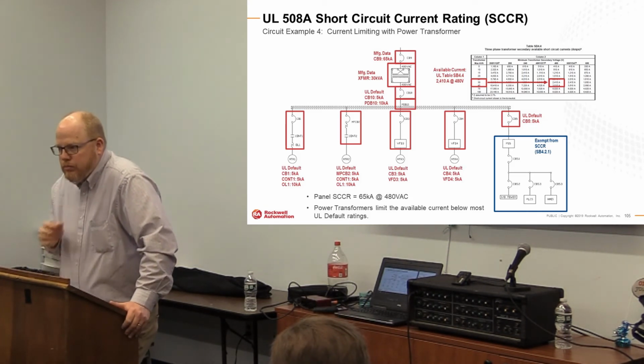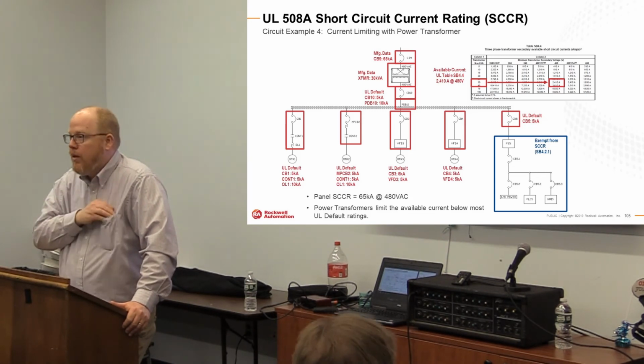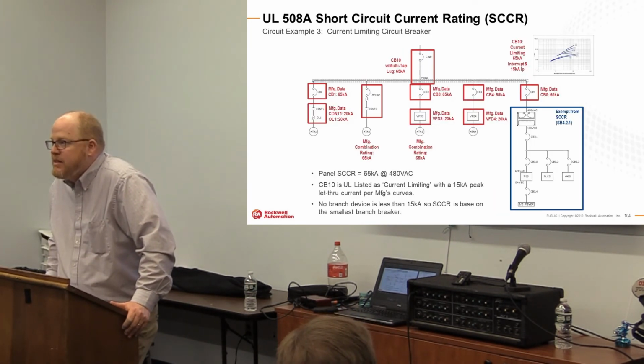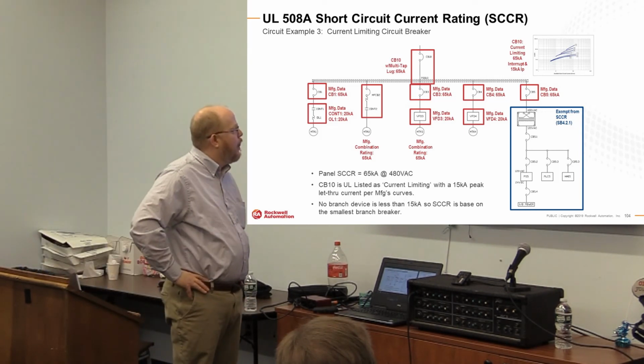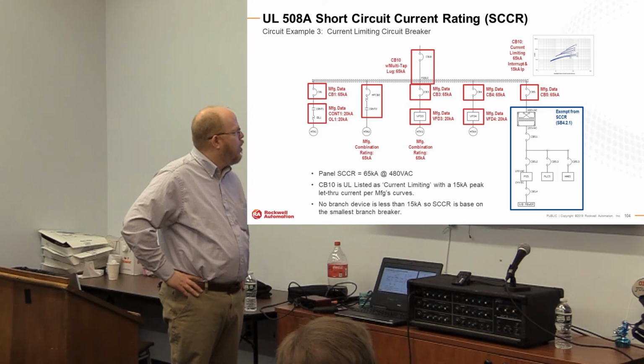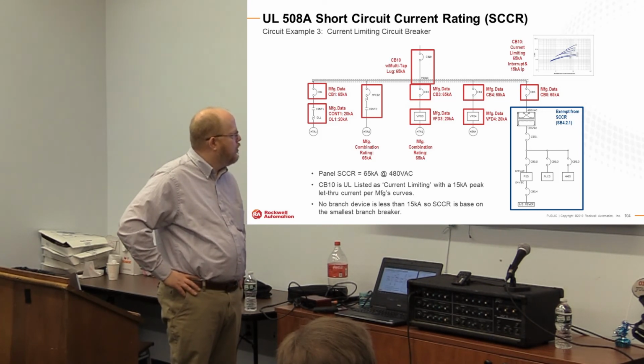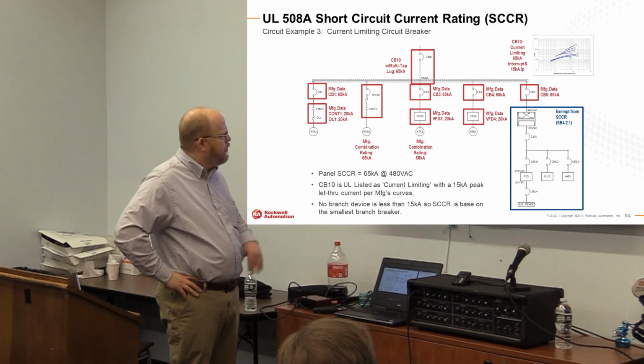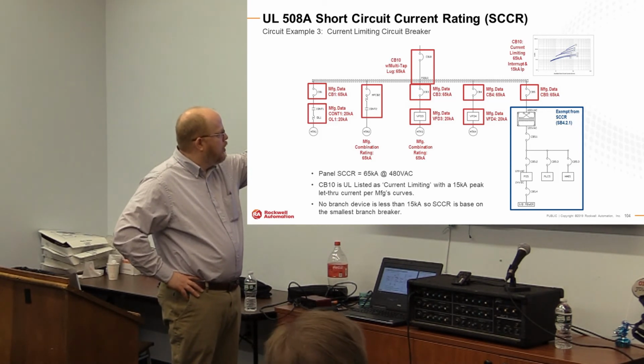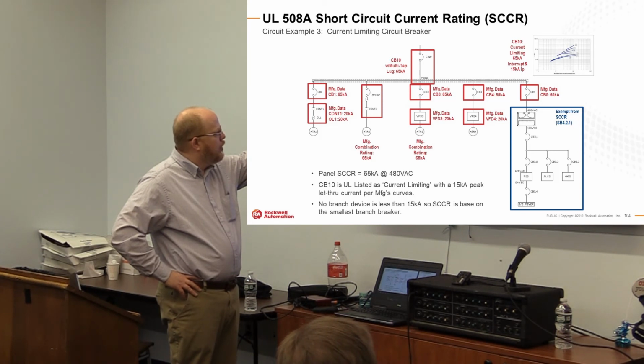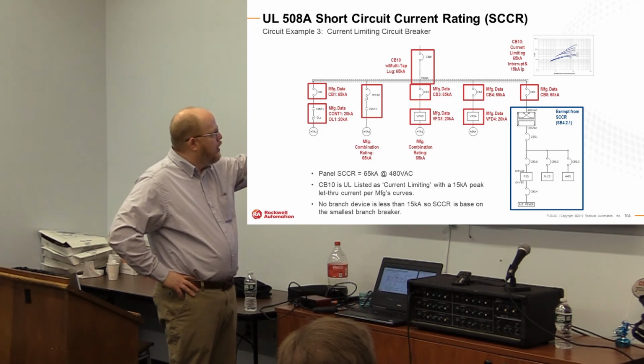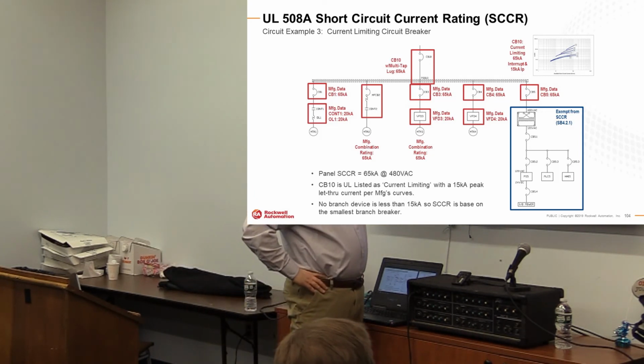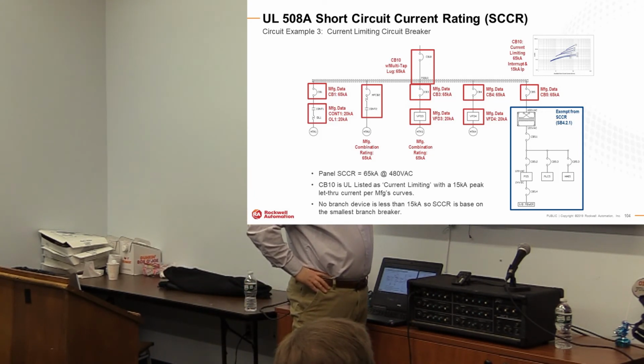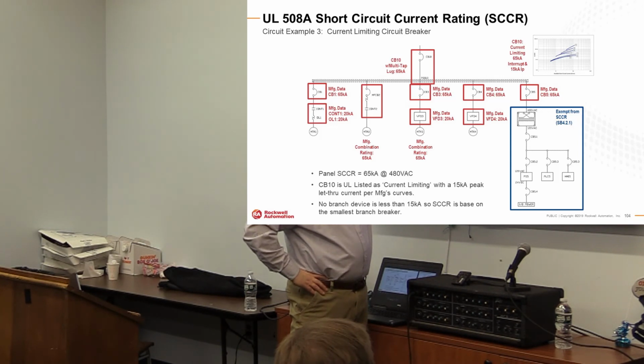On your last slide there, you were trying to reduce the rating of the panel. You wanted to try to reduce that main lug, the 65 kA. You can reduce that to your 20 kA to match your lowest one, then all your other ones would be satisfied as well? Which one again? For your main one that has a lug at 65 kA, if you were to replace that breaker with one that was rated at 20 to match your other branch, well, no, VFDs. No, because this guy is setting the limit for the interrupt rating. Right. So, but that isn't the short circuit rating for the arc flash for the panel? Or am I missing that?